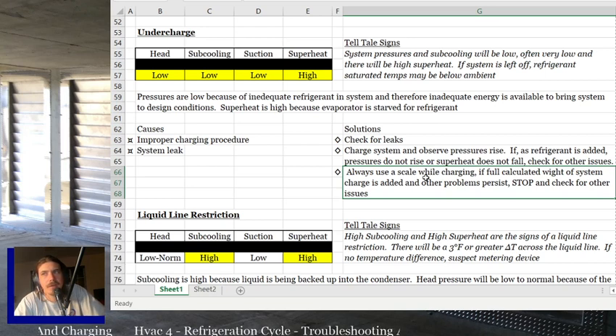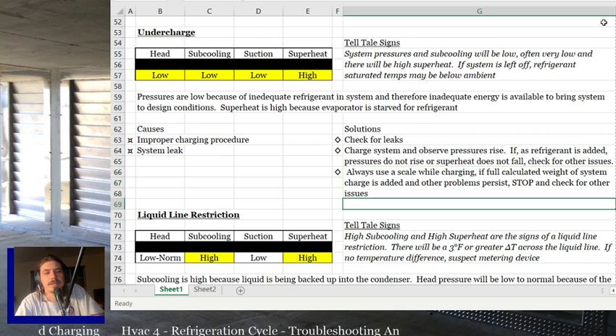If the full calculated weight of system charge is added and the problem persists, then stop and check for other issues. A lot of guys see high superheat and assume low on charge. You shouldn't assume low on charge just because of high superheat or low suction pressure. That's how low evaporator load gets turned into an overcharge. A dirty filter can get turned into an overcharge real quick if you're not checking superheat and you're just checking pressures.